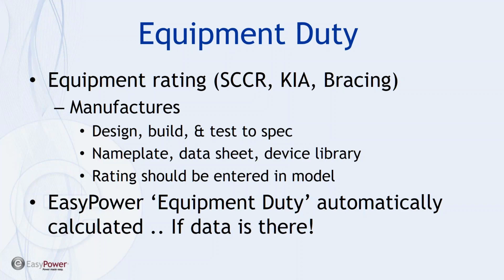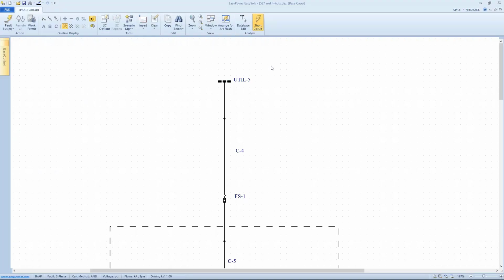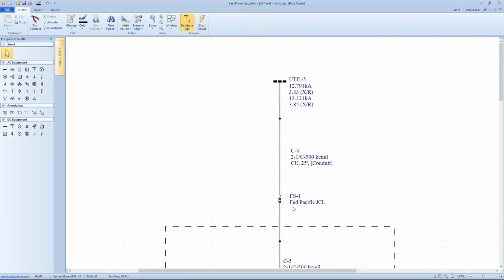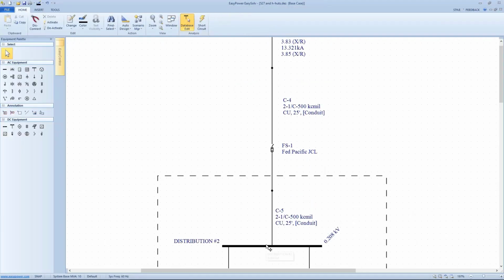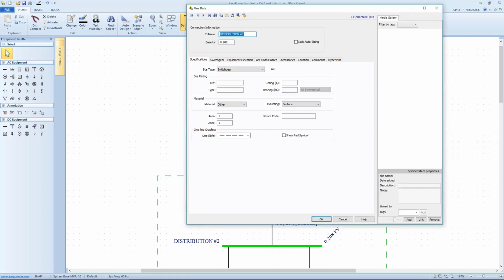Now, jumping back into the tool, that's kind of how I look for that. What we see, for instance, is that this particular bus has on its data dialog box a bus rating for basically the current carrying capacity, and then the bracing rating, which is again the maximum current that the piece of equipment is guaranteed to work within properly. So if this data is not there, we're not doing that check.